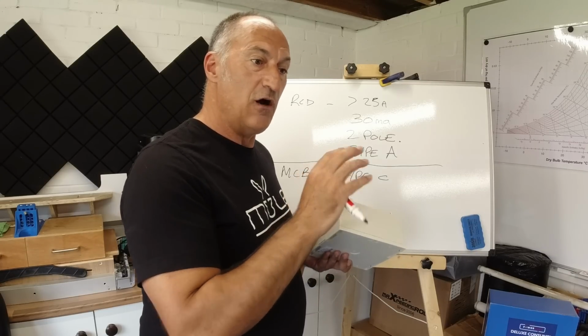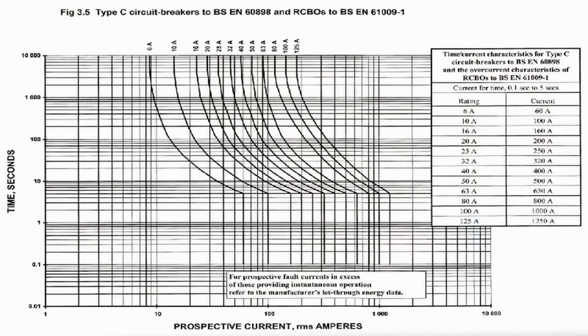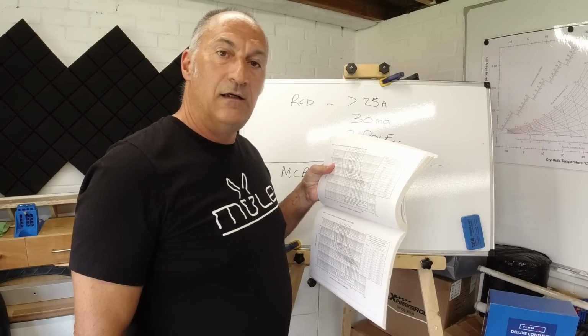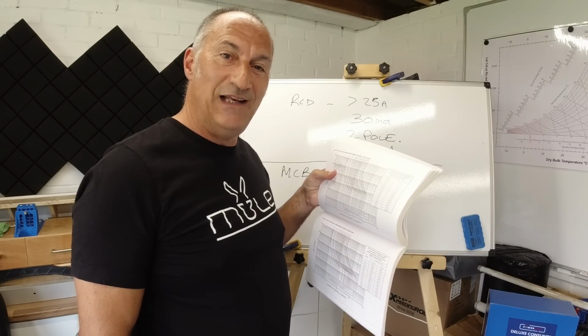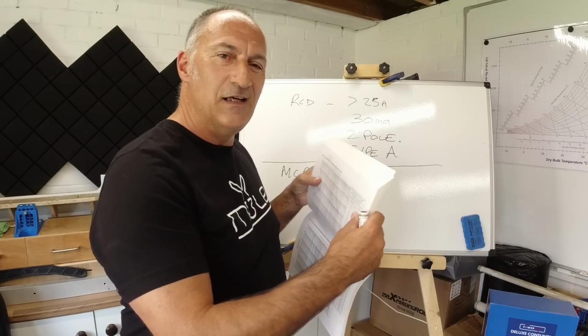And there's a chart in the back of the British Standards for these particular devices. For a type C MCB of different amp ratings, there's a curve on the chart, and you can look at the overcurrent and it will tell you exactly how long it will take before that MCB trips out. Further down the chart it will tell you at what current the MCB will instantly trip. Some of those currents will be extremely large and quite surprising.